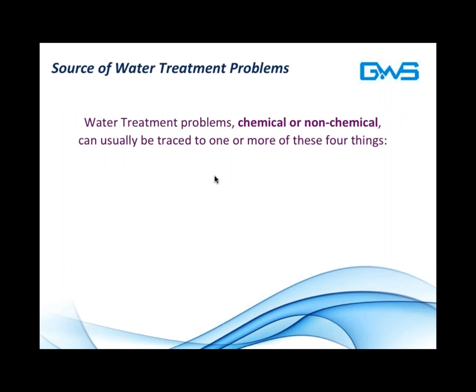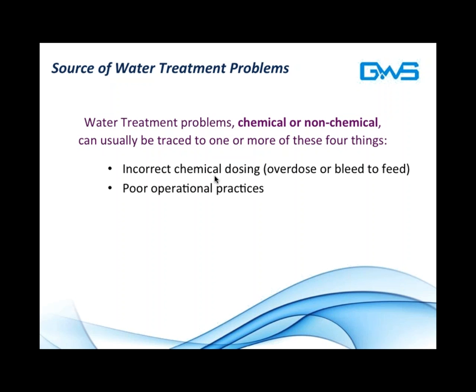Water treatment problems, whether they're chemically related or non-chemically related, are usually attributed to one of these four things. In the case of chemicals, incorrect chemical dosing. This happens often and can result in the premature end of the tower's life, especially with slug dose oxidizing biocides, which can create problems in a cooling tower basin, for example, and pitting. Poor operational practices on behalf of owners and operators, because the cooling towers are out of sight, out of mind. This happens many times. Ineffective solids management, which can lead to breakouts of Legionella and other biological growth within cooling systems. And inadequate monitoring or monitoring service of the tower. So not necessarily knowing what's going on with the system because no one's paying attention to it.